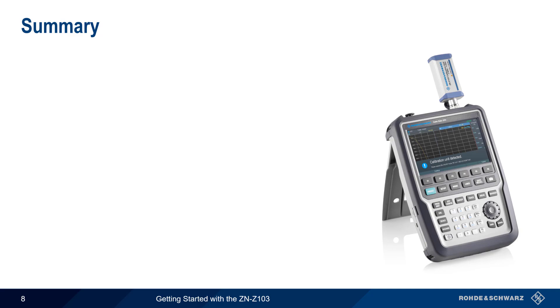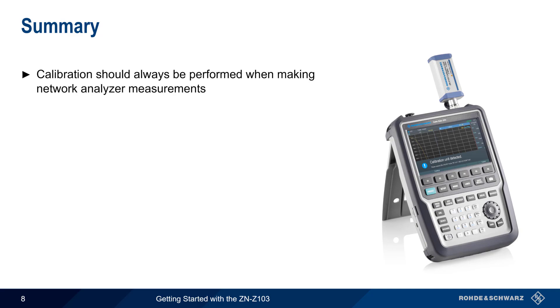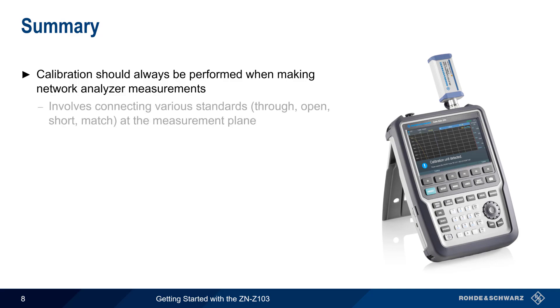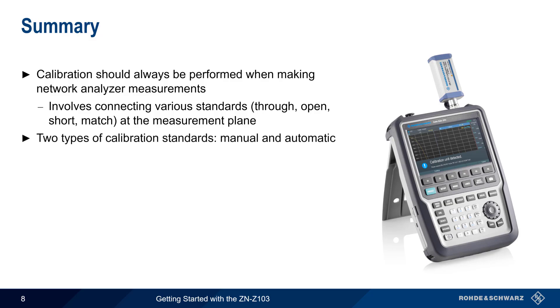Let's end with a brief summary. Calibration is vital for accurate network analysis and should always be performed before making measurements. This process involves connecting various standards, such as open, short, and match, at the measurement or calibration plane. These standards can either be manually connected and disconnected, or can be automatically switched in and out with an automatic calibration or Auto-Cal unit.